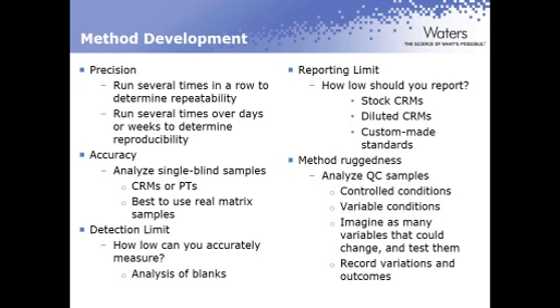Also in our method development, we need to determine our detection limit. How low can we accurately measure? So if we're reporting something on a report to a customer, we can say, hey, we're confident that we're accurate in the determination and what we're reporting. So we've got to determine a detection limit. There's a couple of ways of doing that. Simply enough, analyzing blanks, determining the difference between my instrument noise and an actual signal that I'm seeing.